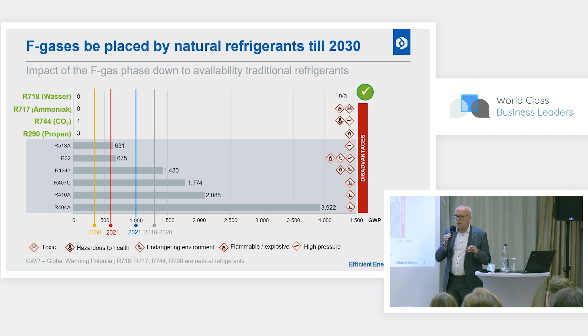CO2 is a high pressure refrigerant and not easy to handle. Ammonia, if you breathe it strongly, you will never get up again. And then you have water, which is a really charming refrigerant. It's not suitable for everything—you cannot freeze systems or make a deep freezing device with water—but it's very charming because it's completely harmless.